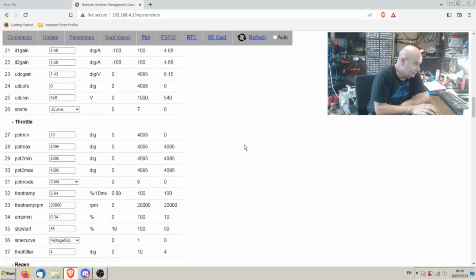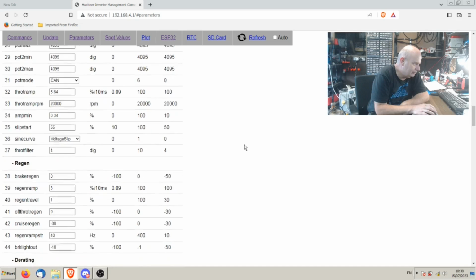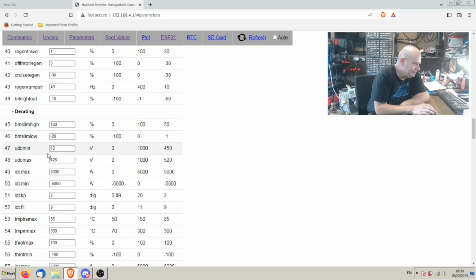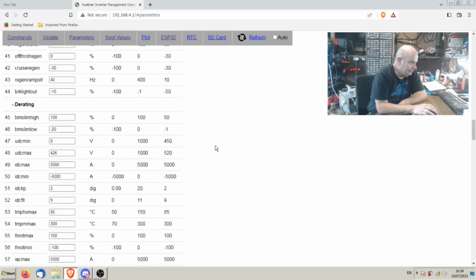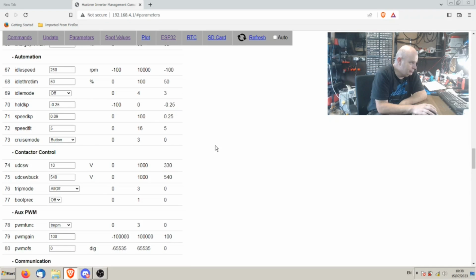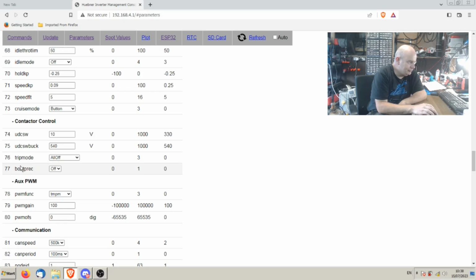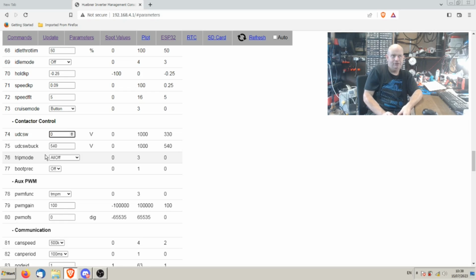Next we want to come down to derating, where we have one called UDC min, and we're going to set that to 0 temporarily. Then we come down to contactor control, and this is the trip mode I was telling you about before. You can ignore that now since we've no contactors hooked up anyway. I'm going to change UDC SW here to 0 and press enter. So what that has basically done is remove any of the high voltage lower limits from the inverter.